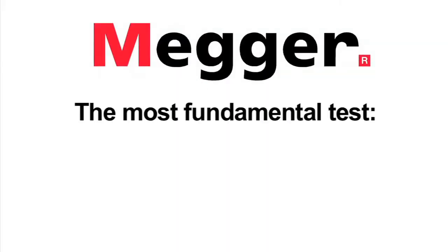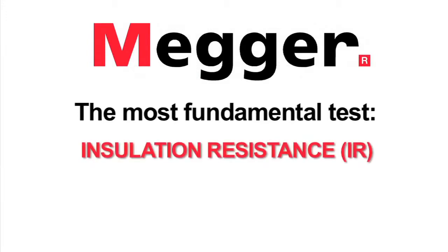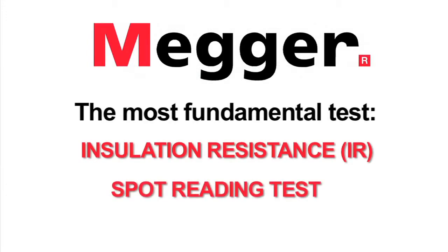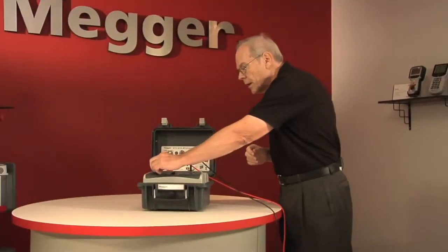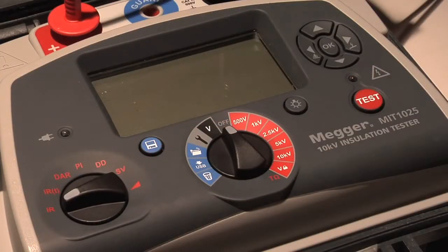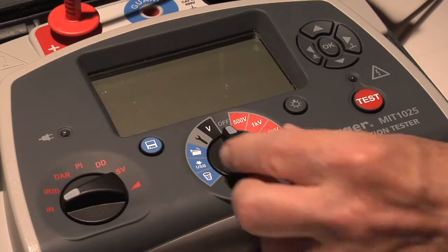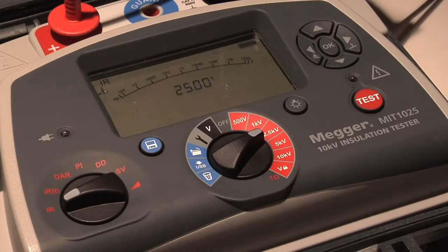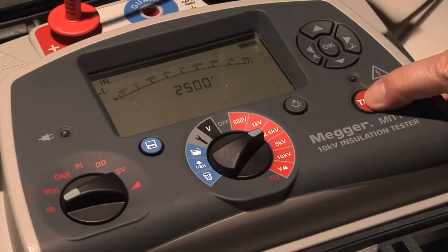The most fundamental test is the insulation resistance IR or spot reading test, so we'll begin with that. The convenient selector switch position sets the IR test, and you set your test voltage based on the rated voltage of the test item. In this case, we'll do a 2.5 kV test. All you have to do then is press the test button.